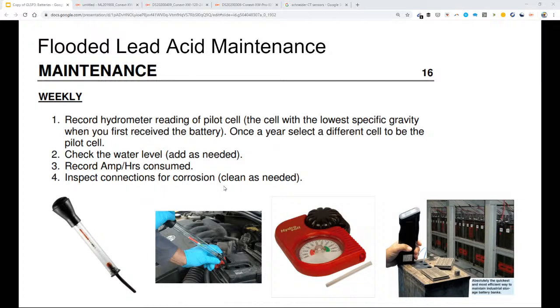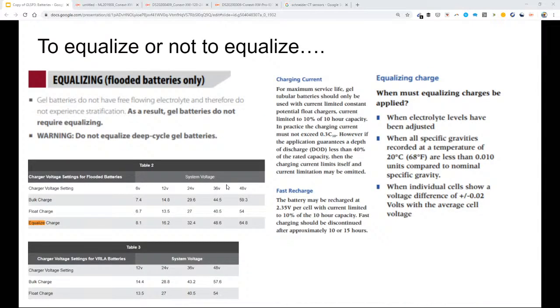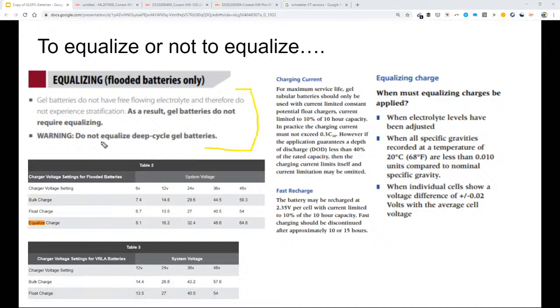At any rate, we're going to leave the maintenance and battery discussion for an off-grid discussion held at a later time, because none of this is something you're going to worry about, since customers for grid-tied batteries - lithium ion is well in the lead. So all I would say is sometimes the literature says sealed batteries do not need equalization. Equalization, that aggressive charge you apply to an unsealed battery, helps it last longer, resulting in longer cycle life ratings on the spec sheet. So it's not really an advantage of a sealed battery that you don't need to maintain it - it's just a difference, and it results in a more expensive battery.